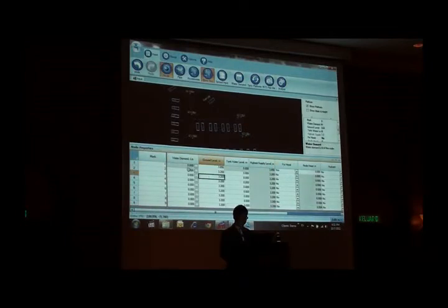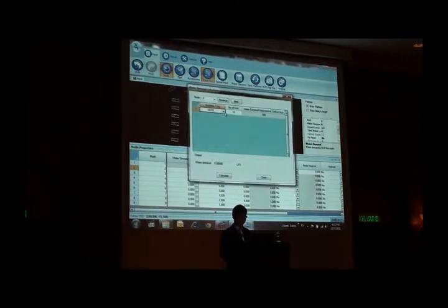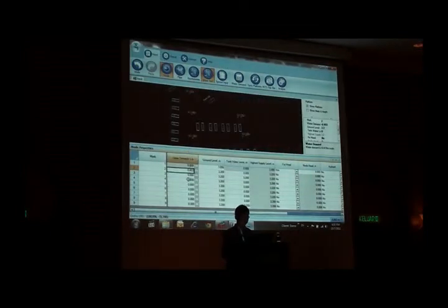Okay, so next step is to input the water demand. Okay, for node number 2, let's say cover double story terrace house, 20 units. Also cover bungalow, 5 units. Okay, so we get the liter per second. Okay, 0.453 liter per second water demand. Okay, I won't do one by one. I just right click. Apply all. Okay, I say assume all is the same.